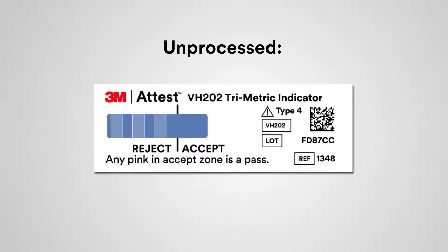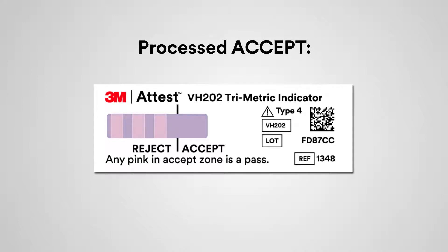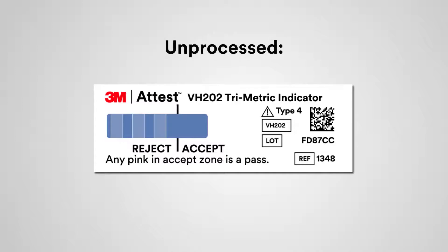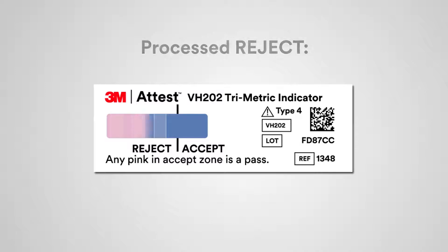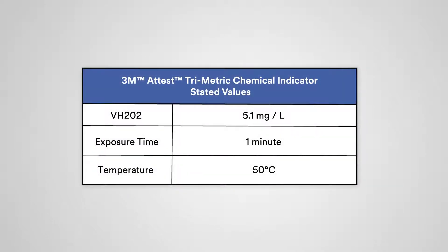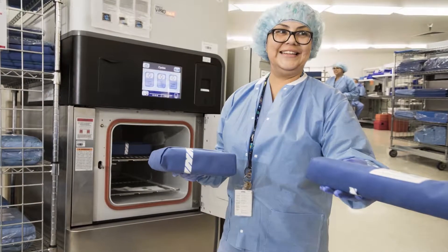Because our CI has a clearly labeled Accept and Reject zone, after processing you should see a color change toward pink in the Accept window of the 3M Attest Tri-Metric CI. If a color change toward pink has not entered the Accept window, a Reject result is indicated, and the items in the pack, container system, or tray were not exposed to sufficient vaporized hydrogen peroxide sterilization conditions. These items should be returned for reprocessing per facility policy and procedures.